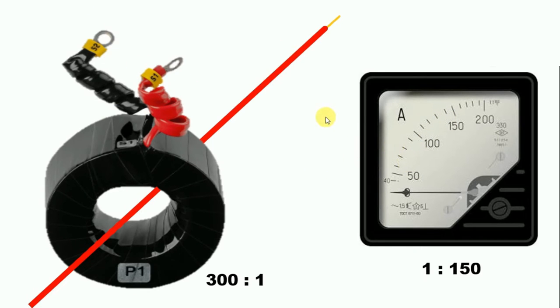Now the ammeter will convert this 1 ampere into 150 ampere or 300 ampere, as per its ratio. So what we need to do is select the ammeter as per the CT ratio.